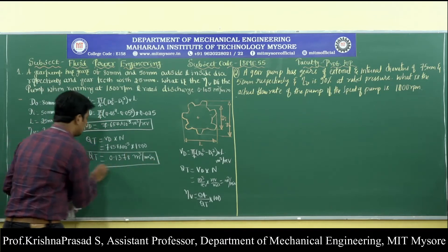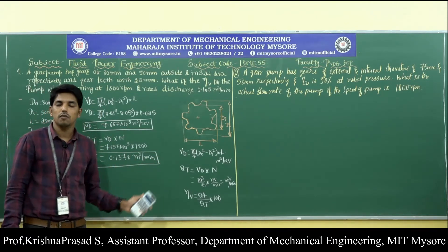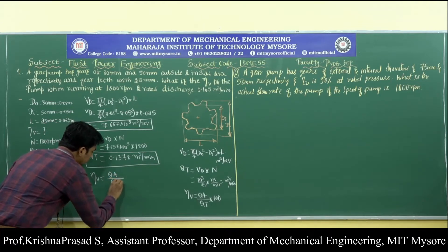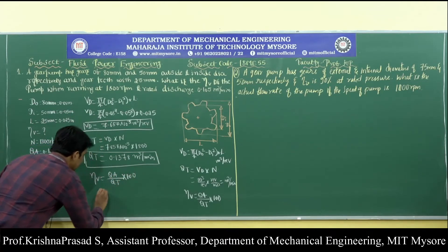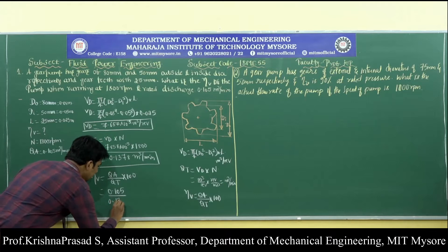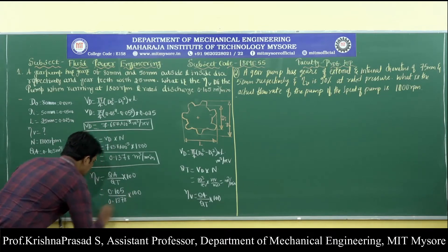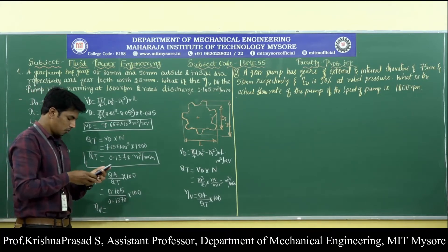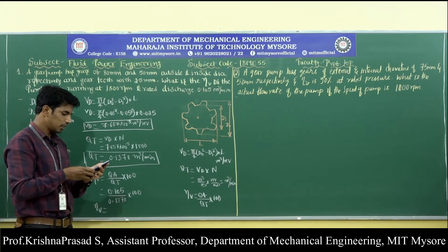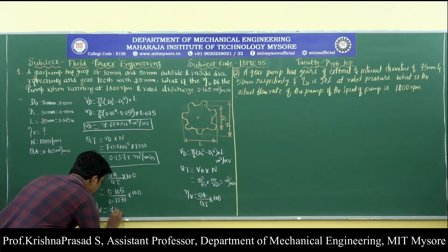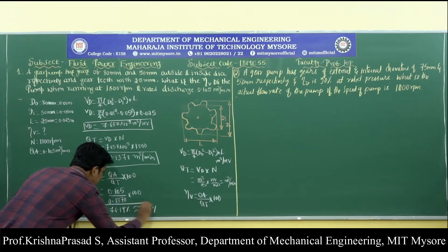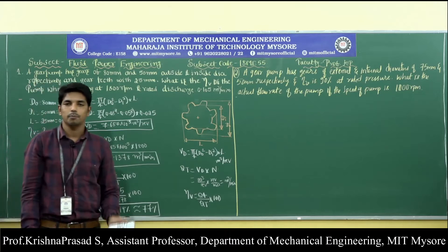The volumetric efficiency of the external gear pump is: η_v = (QA / QT) × 100 = (0.105 / 0.1378) × 100 = 76.19%, approximately equal to 77%. This is the volumetric efficiency of the external gear pump.